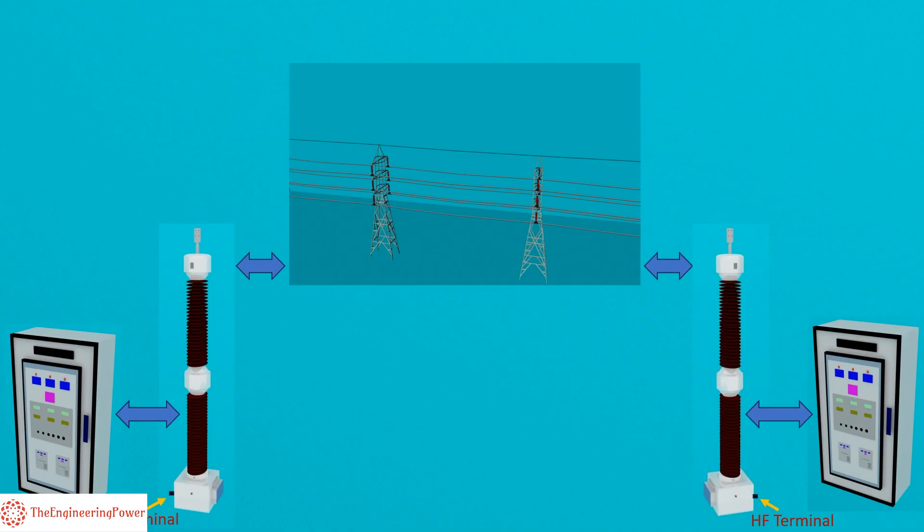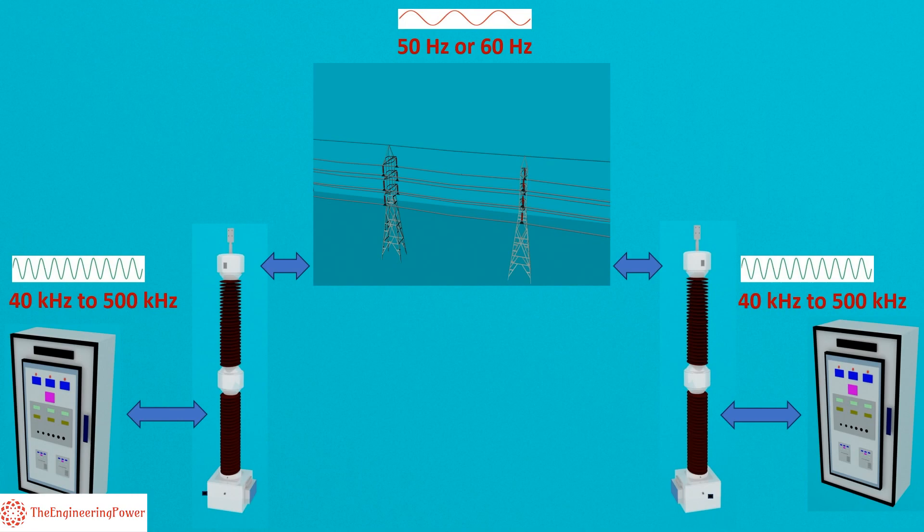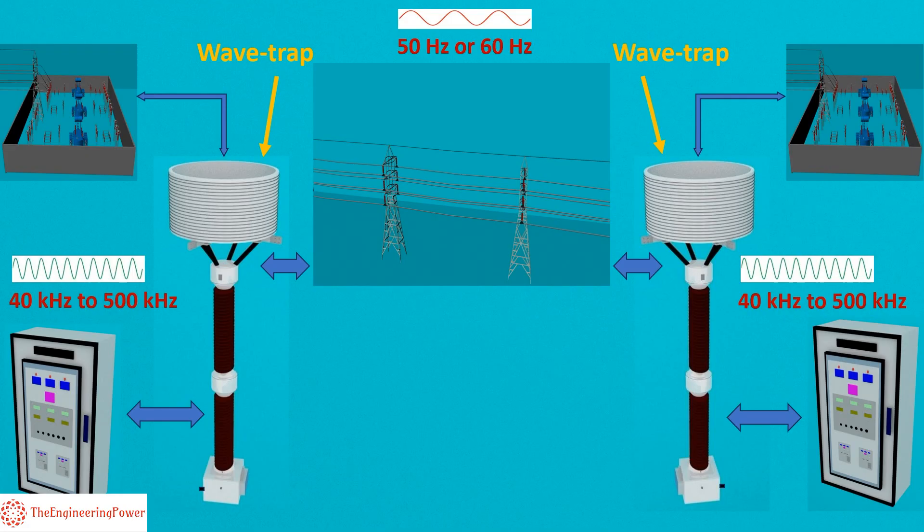However, PLCC uses very high frequencies in the range of 40 kilohertz to 500 kilohertz for transmission of different signals including speech, telemetry, and protection tripping commands, whereas the frequency of power lines is normally 50 or 60 hertz. These high frequency signals must not enter into substation switchyard to avoid any interference with high power equipment. For this purpose, a line trap or wave trap is installed near the connection point of CCVT.